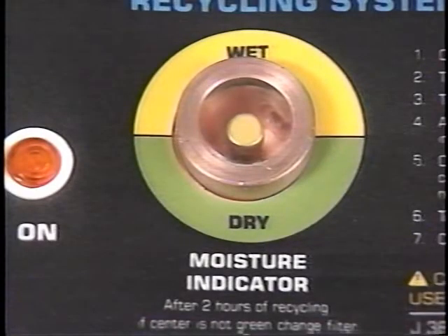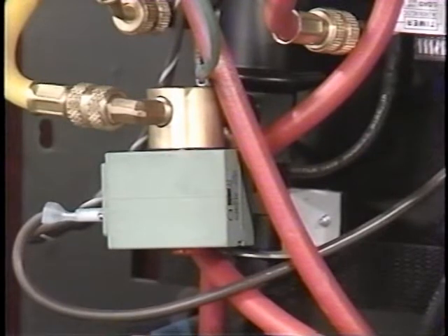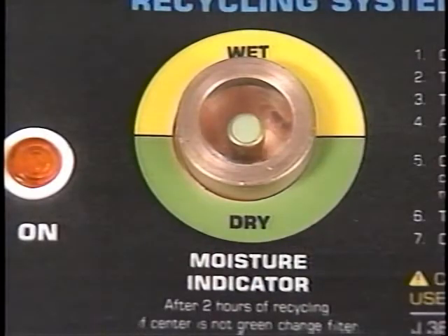Now, every 30 minutes, check the moisture indicator. If it is still yellow, let the system run for up to 2 hours. An automatic air purge system releases air from the storage tank during recycling, accompanied by an air exhaust noise. This is not a refrigerant leak. When the moisture indicator is green, the recycling phase is complete. Close both tank valves and then shut off the power. The R12 in this tank is ready for charging.